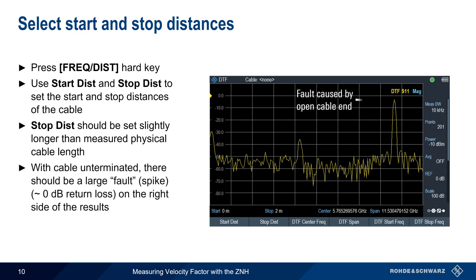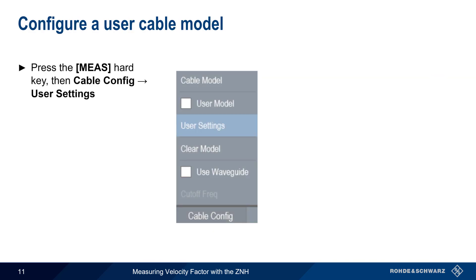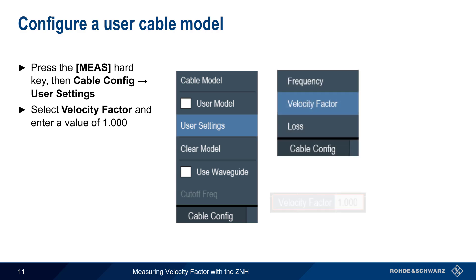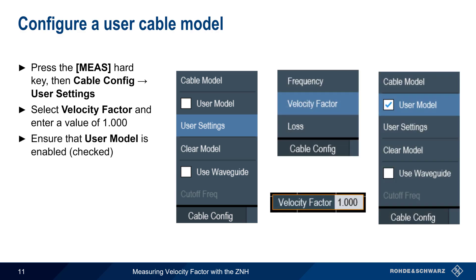If we leave the cable un-terminated, a large fault or spike with close to 0 dB of return loss will be seen on the right side of the results. This peak corresponds to the end of the attached cable. We next need to configure a user-defined cable model by pressing the Measure hard key, then Cable Config User Settings. Select Velocity Factor and enter a value of 1. Be sure that the user model is enabled, that is checked, before exiting this menu.